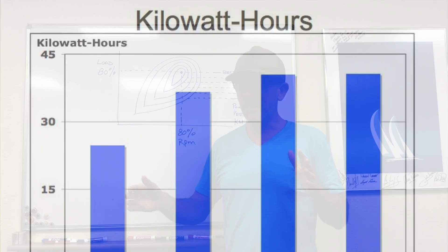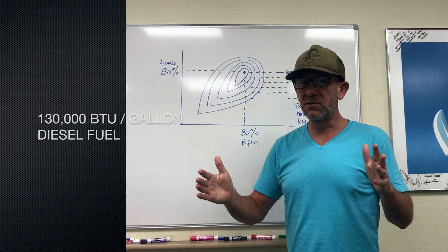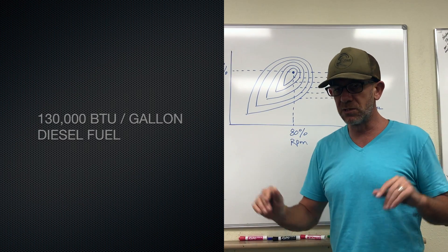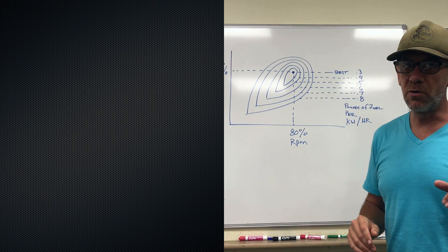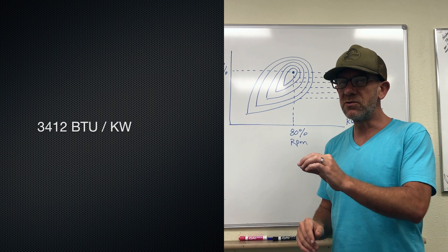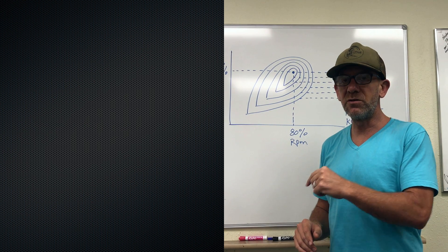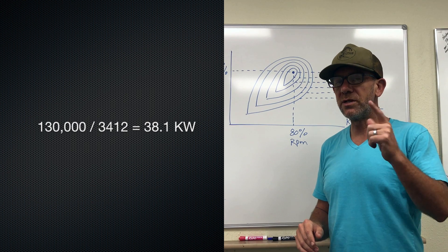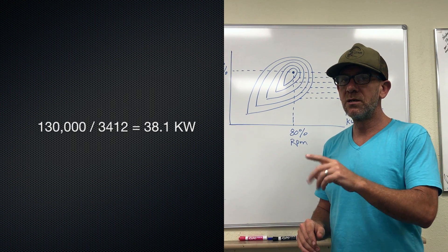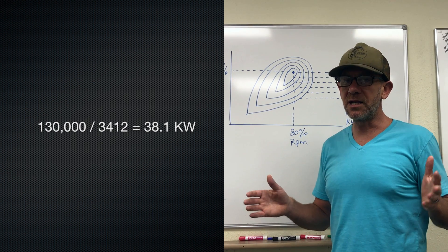What we need to then look at is how much power is available in a gallon of diesel fuel. And we know that's somewhere around 130,000 BTU. That's going to vary a little bit from one diesel fuel to the next, but that's close enough. Now we also know that there's 3,412 BTUs in a kilowatt. So if you divide 130,000 by 3,412, what you end up with is 38.1 potential kilowatts of power in that gallon of diesel fuel.